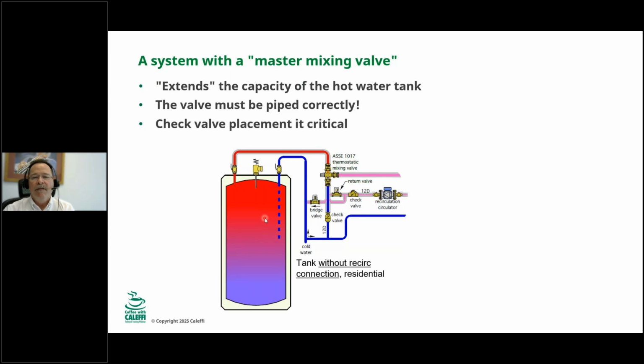correctly when you have a recirc system. So let's talk about that a little bit. Here's just a schematic of a thermostatic mixing valve, and then the circulator is bringing the water back from the system. And you'll notice that there's a check valve here, and let's ignore the return valve and bridge valve just for a minute. That water has to come back to tee into the cold inlet of the thermostatic mixing valve, and that water has to also go back to the tank. So if you don't have a recirc connection on your tank, you can tie that in right here. Okay, and you need to have a check valve down here to prevent that recirc water from going this way. So this is very important that these valves get piped this way.